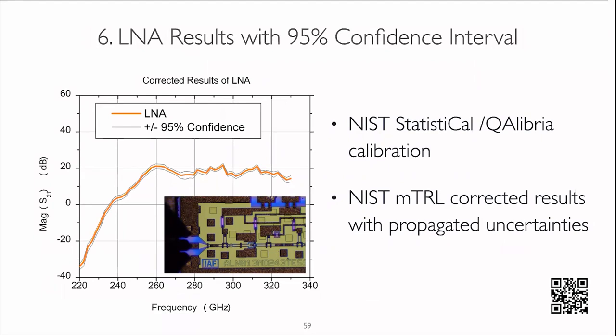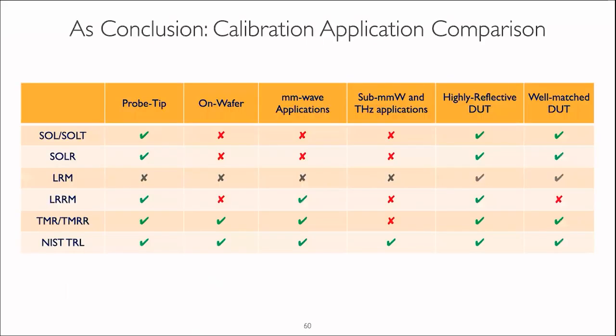The last slide is just a demonstration of what is possible to do using statistical calibration. Here are measurements of an LNA in the frequency range from 220 up to 340 gigahertz, on wafer. This is an LNA from Freiburg, a very, very good technology. What we can see here is that we were able to characterize not only the gain of this LNA, but also to estimate the confidence interval, which makes the transfer of measurement results from one setup to another much, much easier. And this is all possible to do with just one software, QAlibria, and NIST StatistiCAL. We have an application note dedicated to this topic. Feel free to go to the MPI webpage and download it.